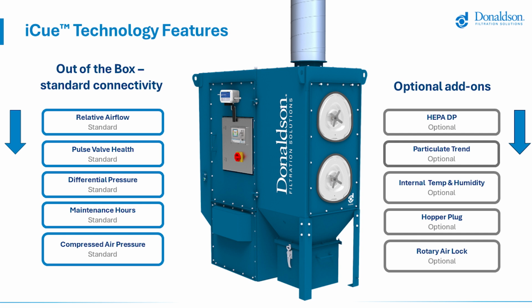So before we go on to how smart connectivity works, let's look at what it can do for you. Out-of-the-box versions allow you to monitor all the items on the left-hand side of the screen. Relative airflow: is the air volume correct? Is it above or below requirements? Pulse valve health: detects pulse valve strength, and on larger collectors where a number of valves are fitted, you can detect any concerns. Differential pressure, the all-important pressure drop, often referred to as delta P. Maintenance hours: records the last service date and the number of hours of operation since. And then compressed air pressure, the all-important cleaning pulse pressure and the performance of it.